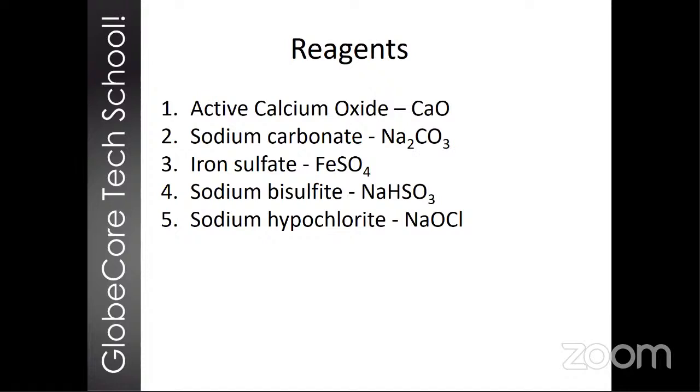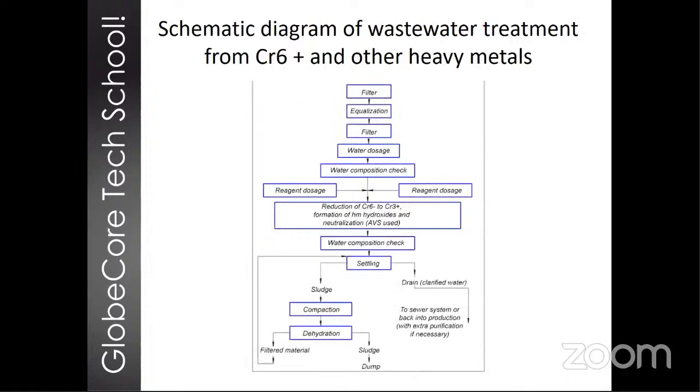To reduce hexavalent chromium to trivalent, depending on the concentration, we use ferrous sulfate, bisulfite, or sodium sulfite as reducing agents. Then we use sodium hypochlorite or bleach maybe to oxidize cyanides and convert them into something harmless. So these reagents are used for wastewater treatment in the form of 5 to 10% solutions. Consumption of recommended reagents for wastewater treatment corresponds to the calculated stoichiometric amounts.